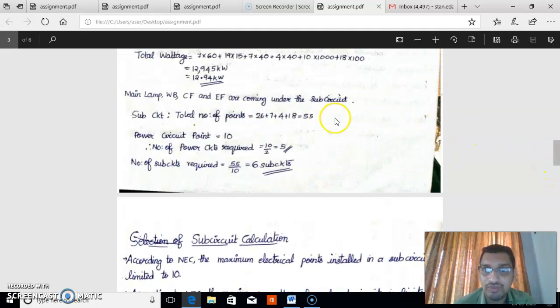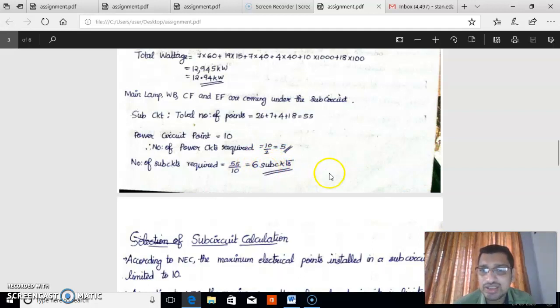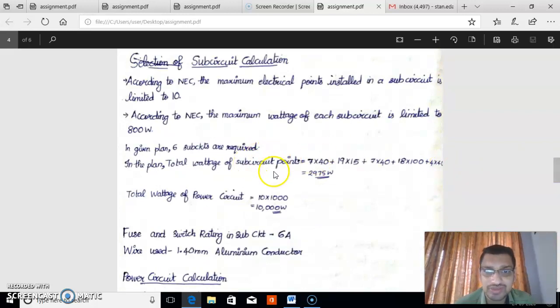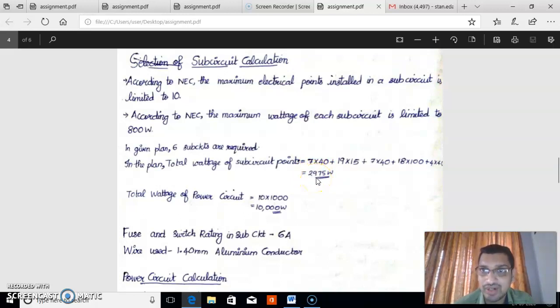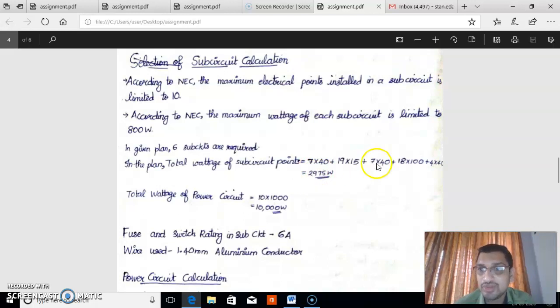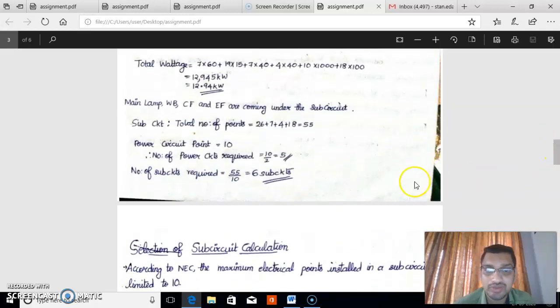In our plan we have 55 sub-circuit points. Since one sub-circuit carries a maximum of 10 points, we need at least 6 sub-circuits (55 ÷ 10 = 6). Checking the second criterion: the total sub-circuit wattage is 2,975 watts. Dividing by 6 sub-circuits gives a value below 800 watts, which satisfies the maximum wattage condition. Therefore, we select 6 sub-circuits.